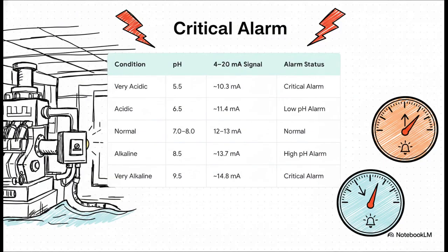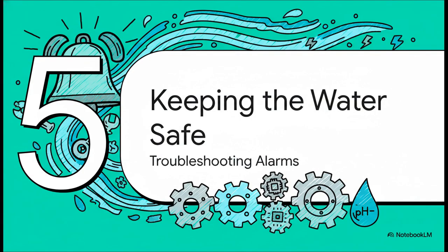So this is basically the cheat sheet for the engine room. As soon as that signal drops to about 11.4 milliamps, which means a pH of 6.5, a low pH alarm is triggered. If it climbs up to 13.7 milliamps, or a pH of 8.5, the high pH alarm goes off. And of course, there are critical alarms for even more extreme values. So when that alarm sounds, it's a call to action. It signals the exact moment where technology hands the problem over to the human element, the skilled engineers who have to figure out what's wrong and fix it before it gets any worse.